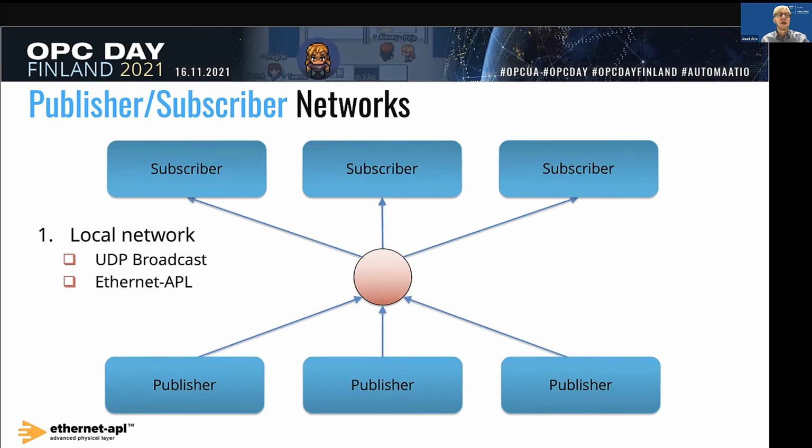And this will be used very much in the new field exchange, I think, in future. In this model, the OPC UA specification defines binary UADP, UA datagram package messages that are very optimized, and you should get the best performance together with the best performance of the network, so that you can really broadcast huge amounts of data if you need to.